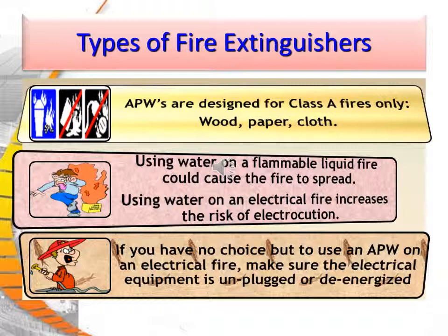Using water on a flammable liquid fire could cause the fire to spread. Using water on an electrical fire increases the chance of electrocution. If you have no choice but to use an APW on an electrical fire, make sure the electrical equipment is unplugged or de-energized.